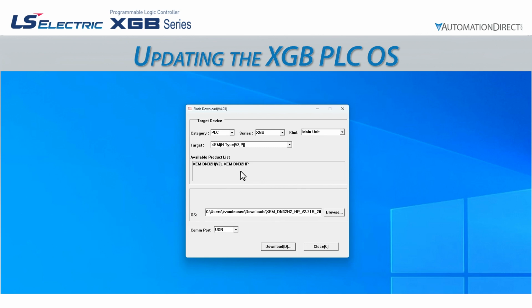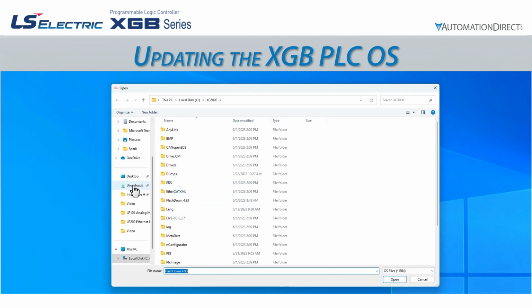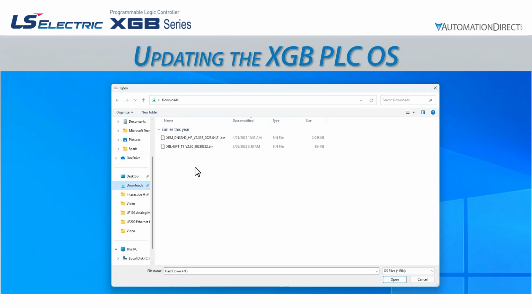As we look at the software interface, we see several fields that need to be populated. We are flashing the OS to a PLC from the XGB series, and it is the main unit. For the target type, we will select XEM. For the OS area, we will click the Browse button and then browse to the Download folder where we have the current version of the OS saved. We select it and click Open.